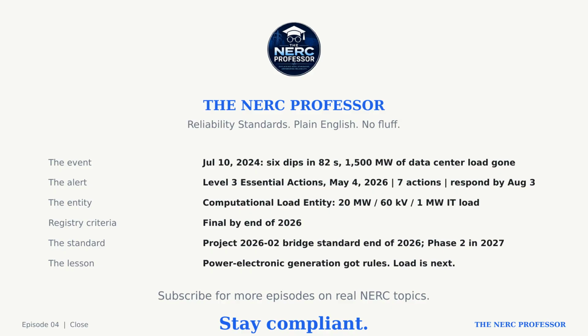Recap. July 10th, 2024. A normally cleared fault, 6 voltage dips in 82 seconds, and 1500 megawatts of data center load walks off the Eastern Interconnection. About 1260 of it stays gone for hours. NERC's answer, 21 months later: a Level 3 Essential Actions Alert. 7 actions. Responses due August 3rd.